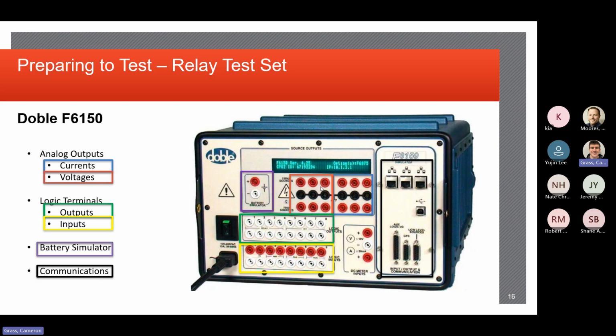These are usually interchangeable. It's pretty common to keep one side voltages, one side currents, vice versa. Your logic outputs, which is the green box right here, are what's going to be picked up from the relay. So if you're monitoring an input or you're trying to see a specific element being picked up, this is what you'll be basically wiring in series to your test set to verify that the relay is operating the correct output or picking up the correct command properly. Kind of the same idea for the inputs.